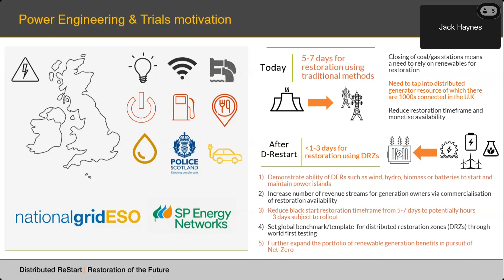As Pete alluded to, there were two earlier trials that were completed last year. The first utilised a series of hydro generators in Dumfries and Galloway in the south of Scotland, a series of 13 MVA generators connected at 11 kV to energise a test network that was isolated from the main grid, all the way up to 275 kV. One of the key figures measured there was the block load pickup capability of the assets. That's the single instantaneous load that we can add to the power island without the island losing stability. That figure is key in giving us an understanding of how much demand we can bring on from the resources we've got at our disposal in the power islands.